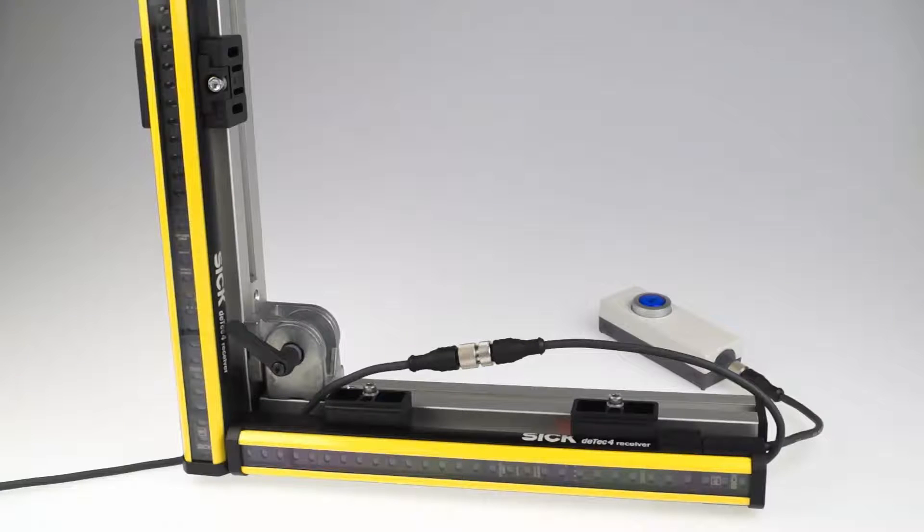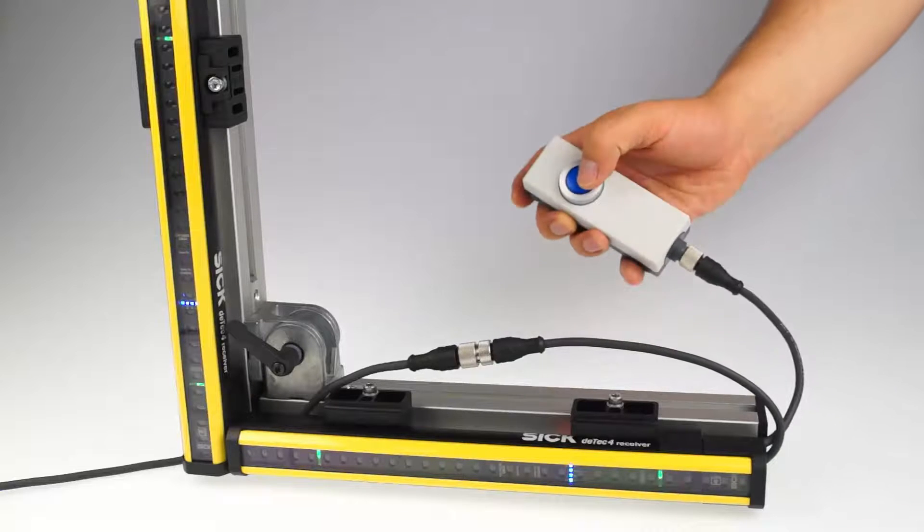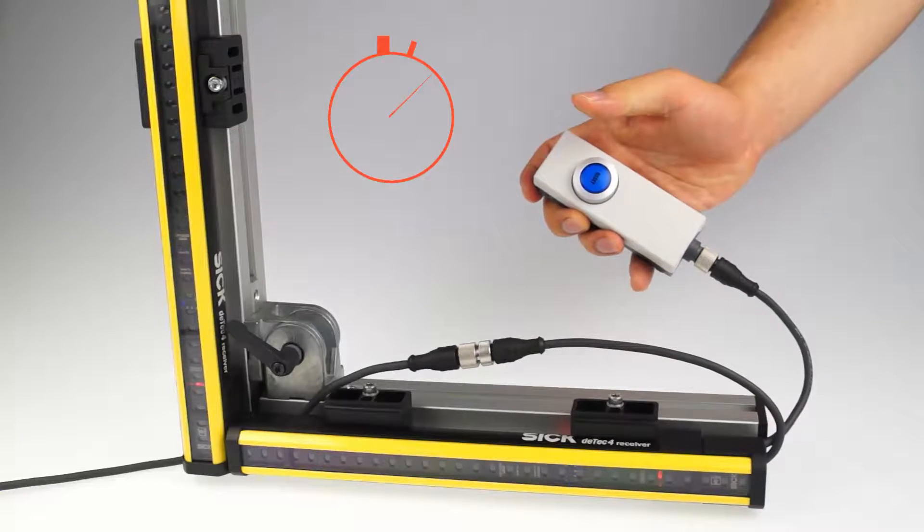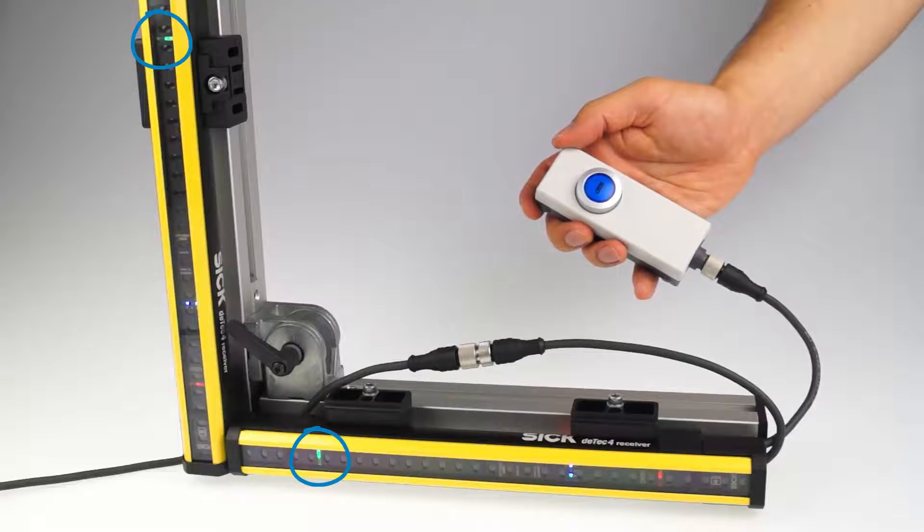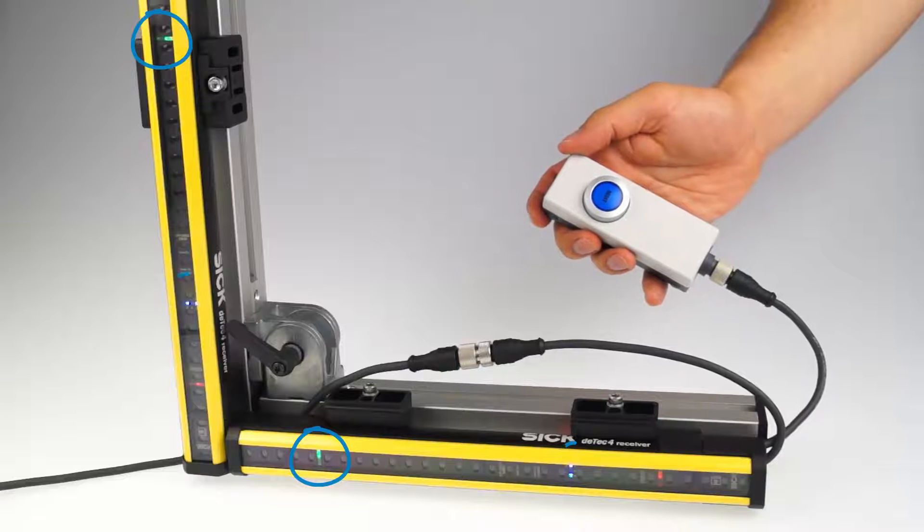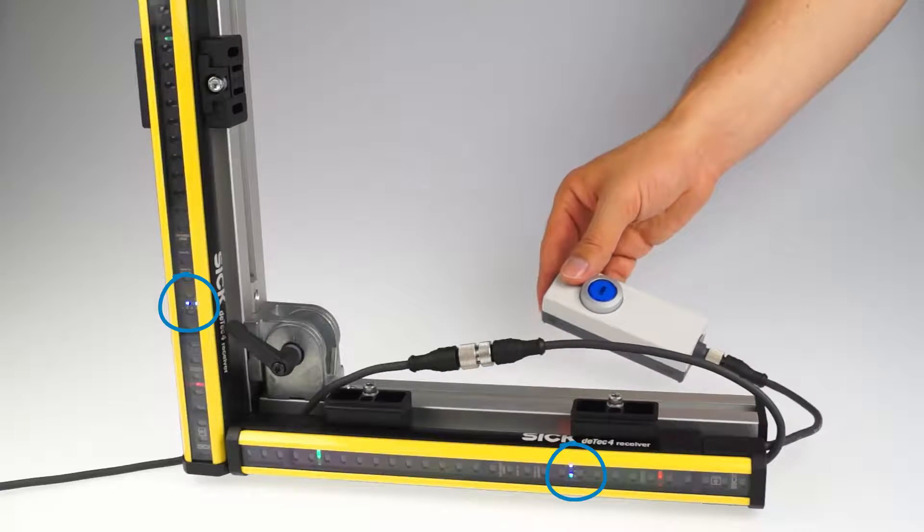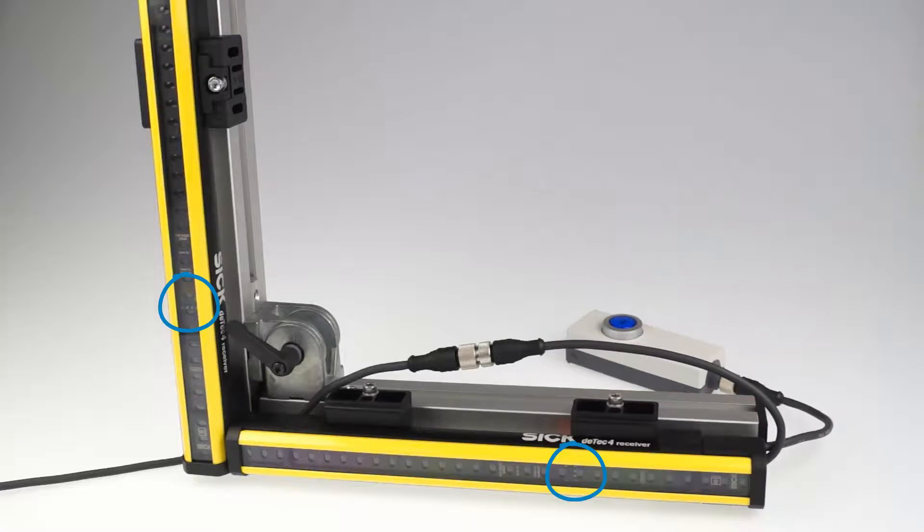Then connect the system again with the power supply. And within 30 seconds you have to press the reset button and release it after 1 to 3 seconds. To signal that the configuration has been successful, the device's field LEDs flash green. The blue alignment LED 4 also flashes to signal that the restart interlock is configured now.